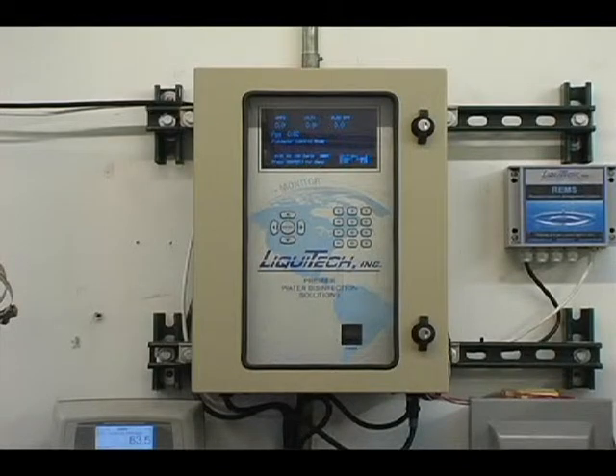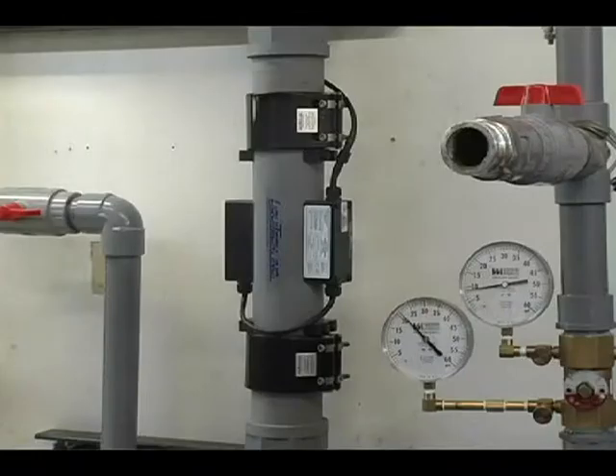The controller uses this flow signal and an algorithm programmed into the unit to determine the appropriate amperage setting needed to achieve the desired amount of copper and silver ions to be introduced into the water. The system reacts instantaneously to variations in water demand by automatically sending a signal to the controller, directing it to increase or decrease the generation of copper-silver ions released from the ionization chamber in order to maintain the optimum targeted levels.